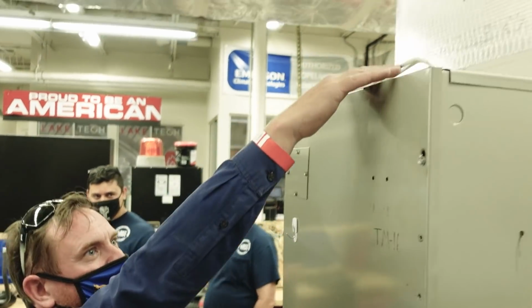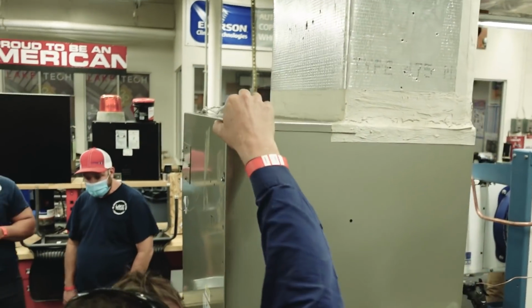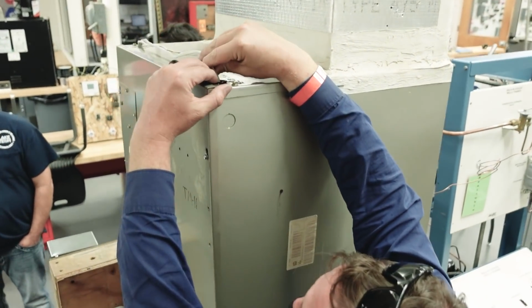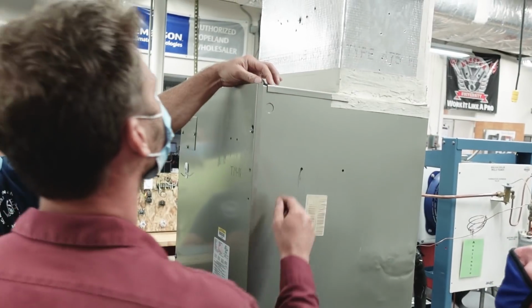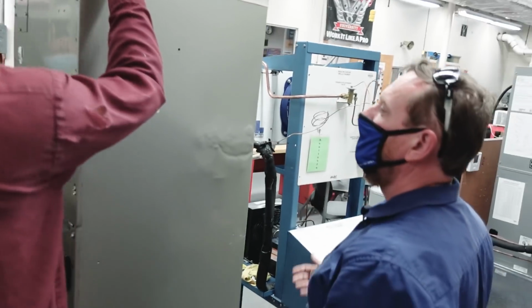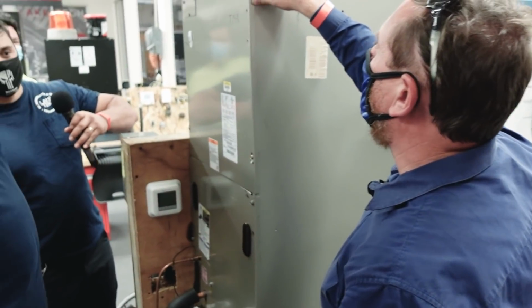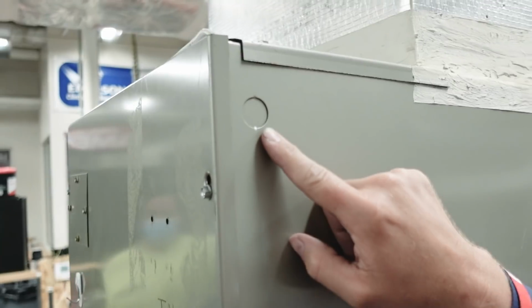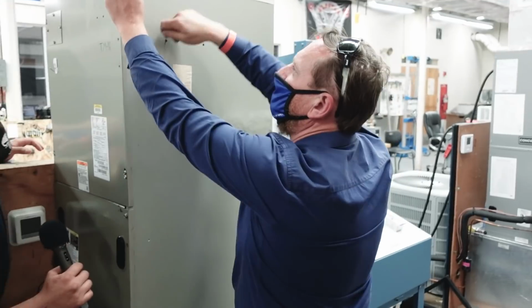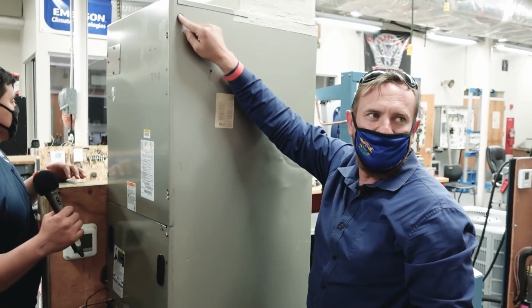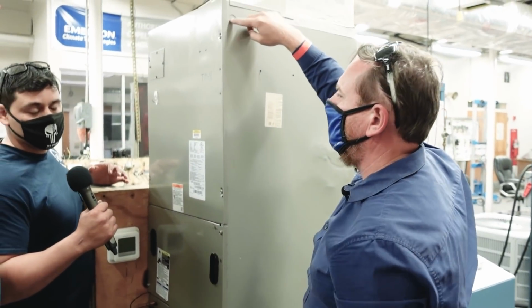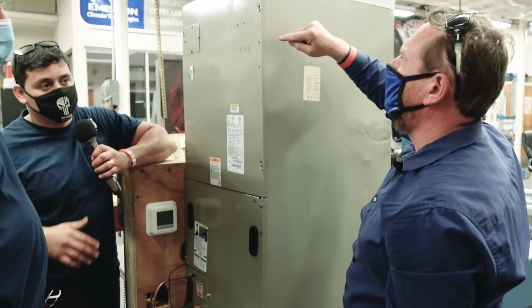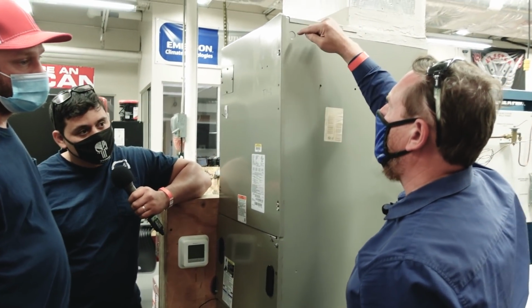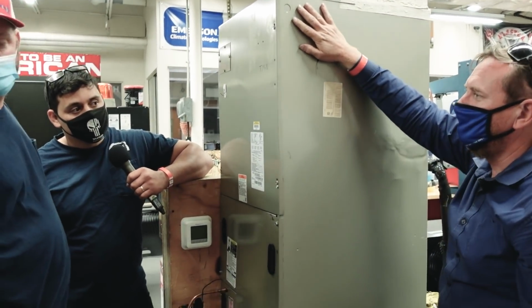If it goes over here, we go around the top, come in here. Let's feel where this wire comes in, is there anything for it to rub on? I'm vertically challenged. Is there a grommet? Yep, good. But look at this little knockout right here, you guys see it? A lot of techs will knock that out and run their low voltage wire through there. Now that wire rubs against it, giving it a short path. Electricity can flow from that low voltage wire to the metal, boom, shorts out. That's an example, so shorts, you're looking for anything like that.